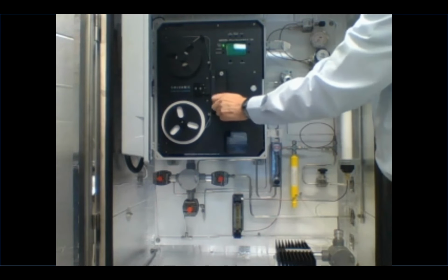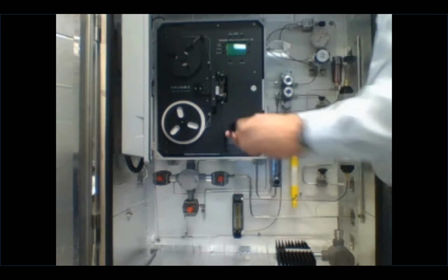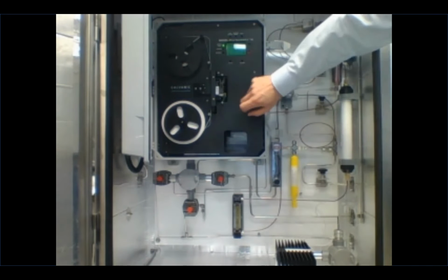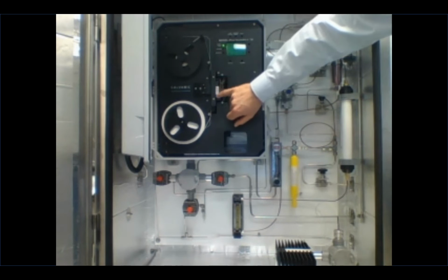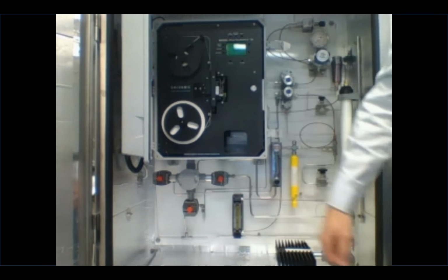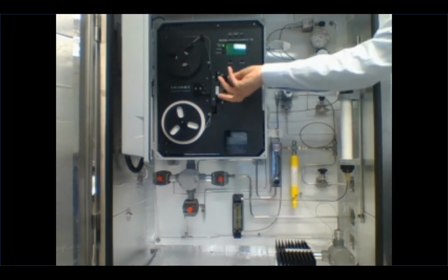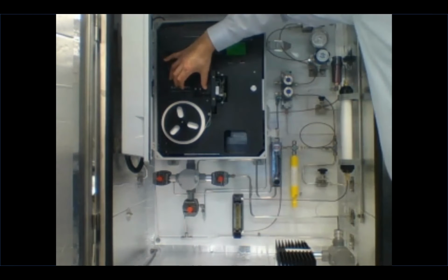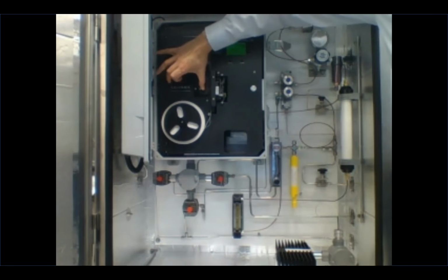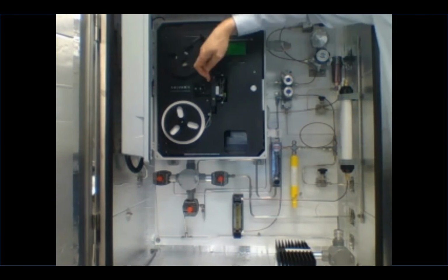This little cover here basically comes off, and this is the sensor block itself right here. So essentially, it's all built into a plastic block, so there's no light alignment or anything like that associated with it. It can only fit into this slot one way. So basically, it just plugs in like that. If I pull back the compression head, you may be able to see on the webcam the red LED shining through.